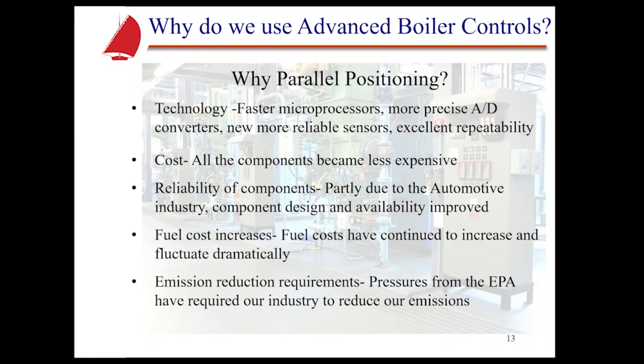Again, why do we have parallel positioning? Well, it's because of the technology. We got faster microprocessors. We got more precise A to D converters. We went from being able to control within a couple of degrees of accuracy to down to a tenth of a degree accuracy. And that's because the A to D converters have gotten better, and that means analog to digital. We went from 8-bit to 10-bit, which gave us 1024 different independent steps. So we can then, again, get into that 0.1 degree of accuracy and repeatability.